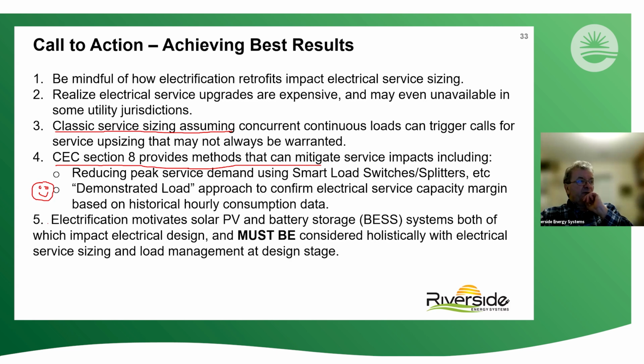Often with electrification, owners are motivated toward solar and storage to reduce their consumption, reduce peak demand, and potentially reduce time of use consumption during the peak demand window. Solar and storage impact the electrical design of the building. So my recommendation is that we must holistically consider not just electrical service sizing, but also integration of solar and storage at the design stage, if you want good results from a retrofit.